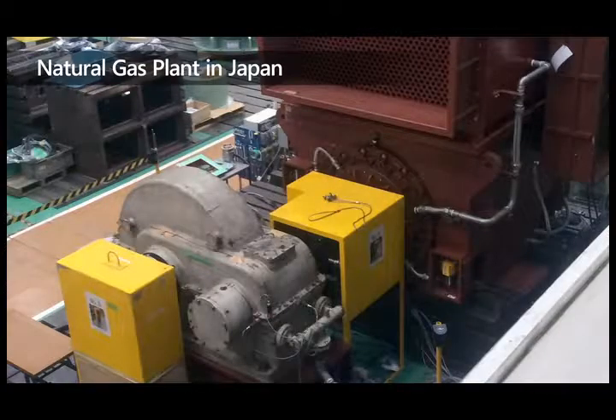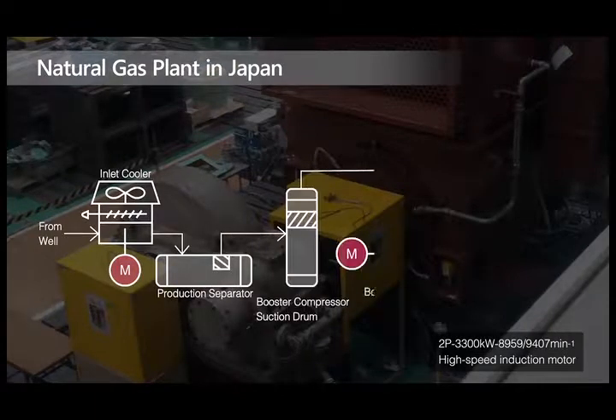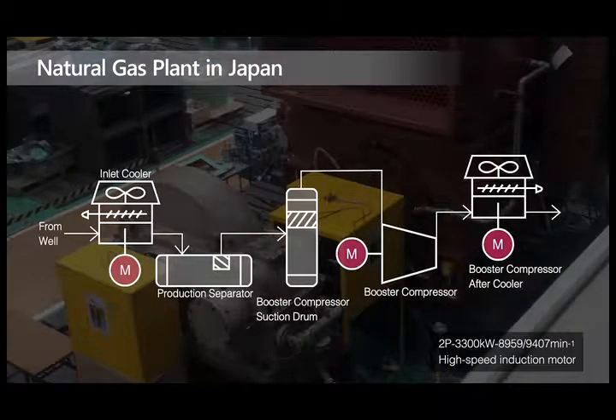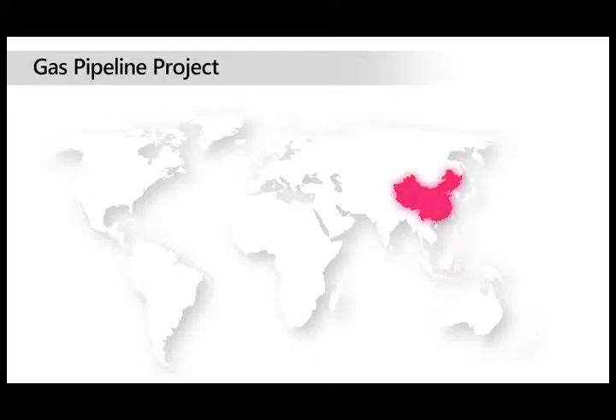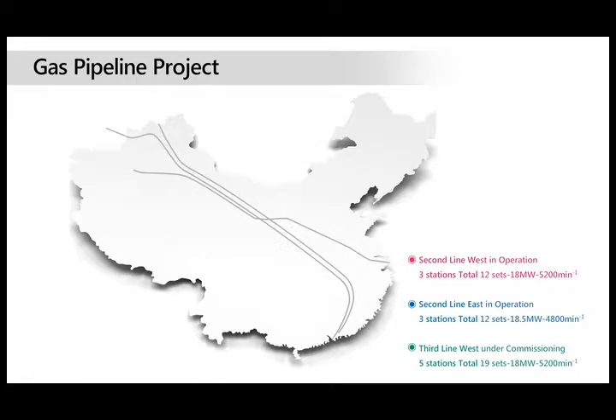Another example is a new project for a booster compressor for a natural gas plant. The project concept is a utility-free solution. So, the choice was an air-cooled motor with magnetic bearings, an induction motor rated 3,300 kilowatt output, 8,959 rotations per minute. TMEIC has successful experiences with motor and drive systems for gas pipeline booster compressors.